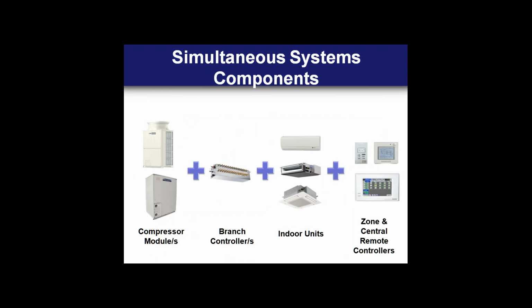Again, looking at basic system components, you have the outdoor system, the air-cooled heat pump, or in the case of the water source module, which will be located inside. Then you have your main refrigerant pipes from those units to the very first thing they would see in these heat recovery systems, which is a branch controller or controllers. There could be more than one. From that branch controller, you'll have separate lines, or dedicated ports, I should say, that feed the dedicated circuits to each of the indoor units.